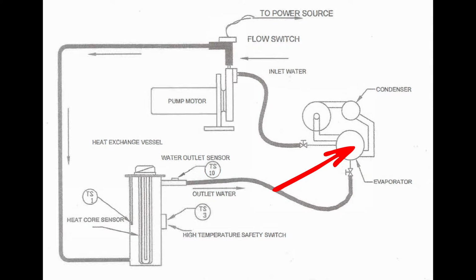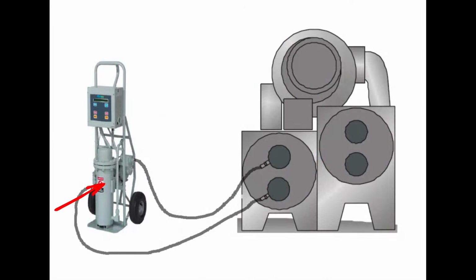Now, what's also really cool about these RefTechs is the pressure sensor will keep everything online to where once you hit your pressure set point, if it sees that it starts to drop below that set point, let's say you were leak searching, you've got a large machine, you wanted to keep it at 5 psig.